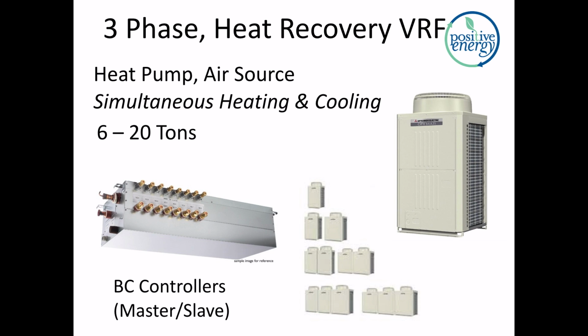Next thing you have is heat recovery systems. So similar form factor, internally some differences. These typically have some sort of branch controller or a three-pipe system in place. But the focus here for you now should be that you recognize that these systems offer the ability to have simultaneous heating and cooling. This can be a big deal where stack effect heating could be occurring, or where the perimeter of a building needs to be cooled, and that means that the center core of a building is needing heating. The heat that's being rejected in the areas asking for cooling can be sent right to the areas asking for heating, and the outdoor unit is essentially acting as a pump in that situation just to move the refrigerant around.